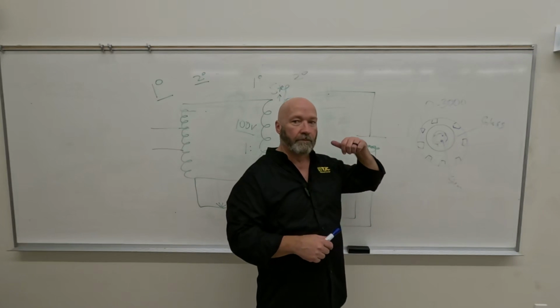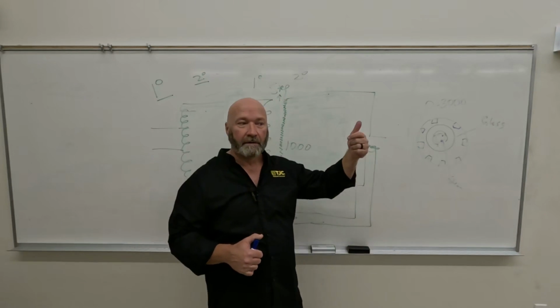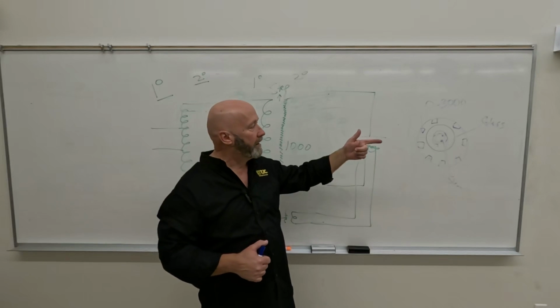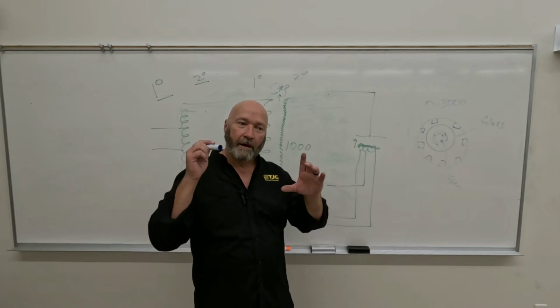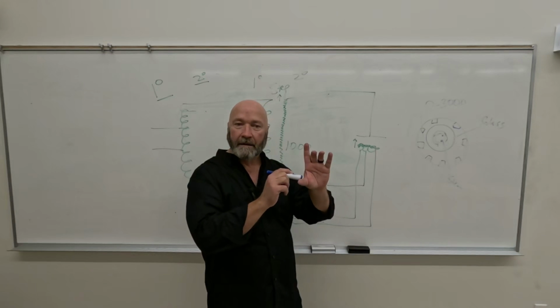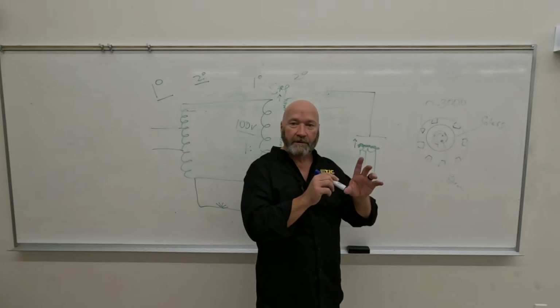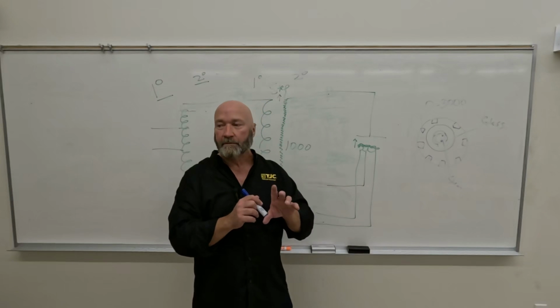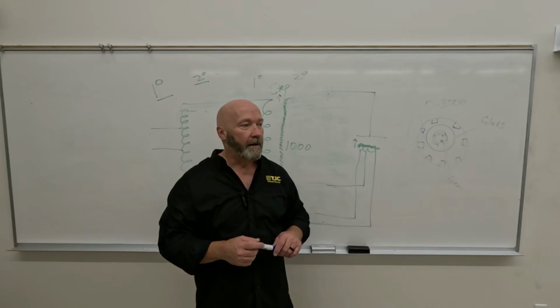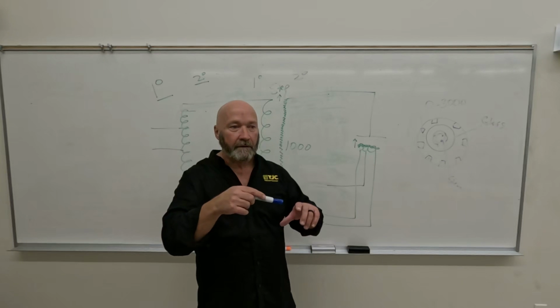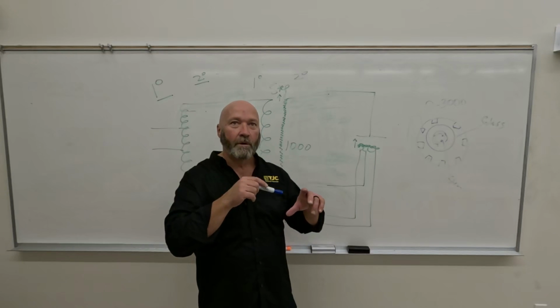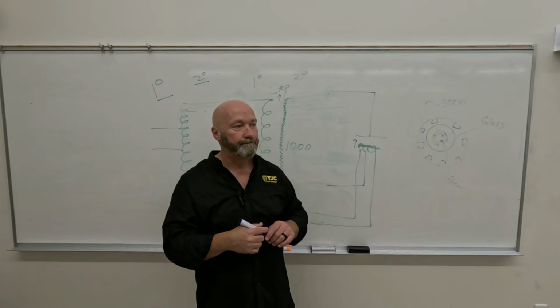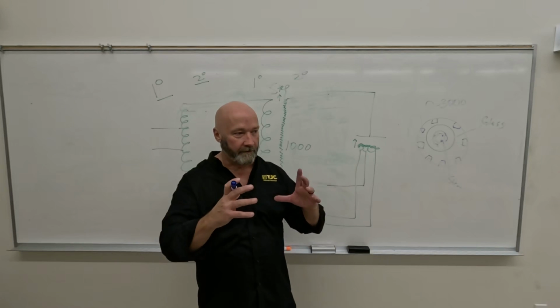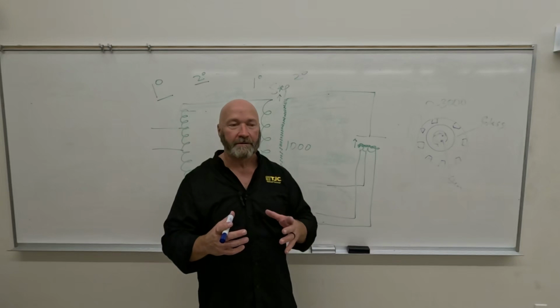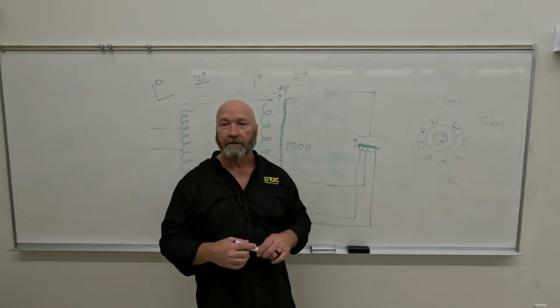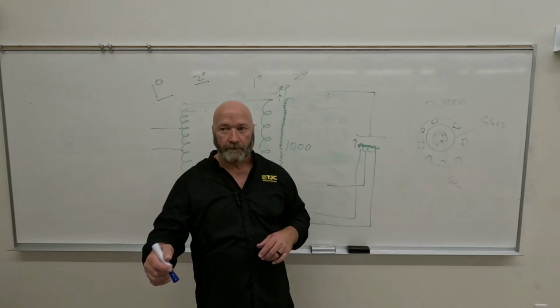We deal with it through convection, conduction, right? So if I put all those electrons in one spot, I don't spin my anode, I put all those electrons in one spot, what's going to happen to that one spot? It's going to burn it up, right? But if I spin it around and around, then where am I putting those electrons? Distribute them all over the face of the anode, or really the face of the target, and then we conduct it across the face of the anode. Reduce the heat load on the tube.